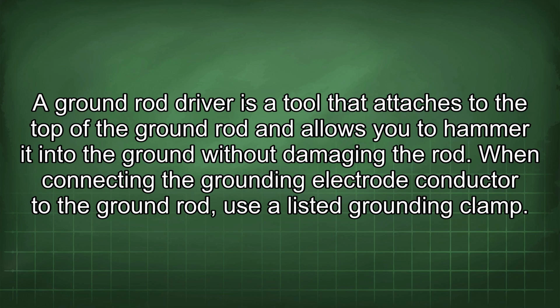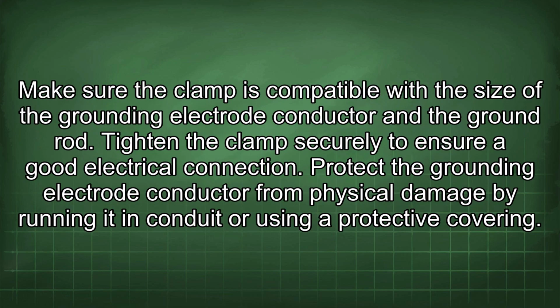When connecting the grounding electrode conductor to the ground rod, use a listed grounding clamp. Make sure the clamp is compatible with the size of the grounding electrode conductor and the ground rod. Tighten the clamp securely to ensure a good electrical connection. Protect the grounding electrode conductor from physical damage by running it in conduit or using a protective covering.